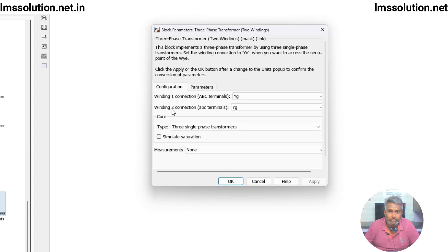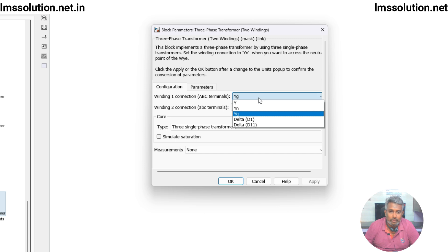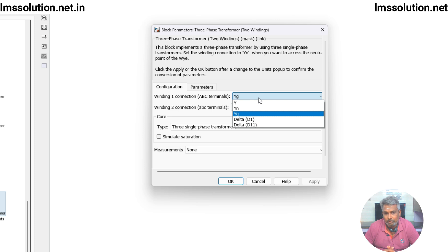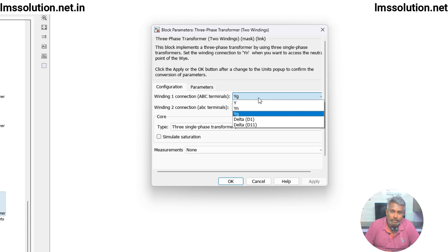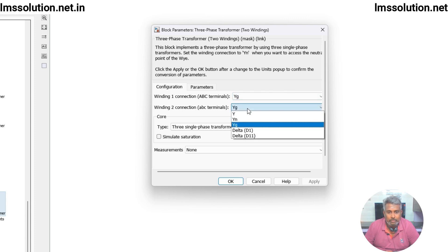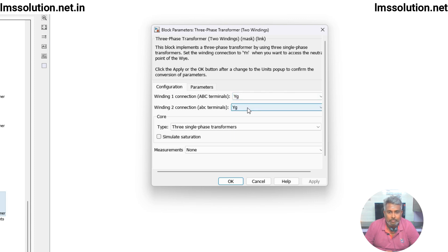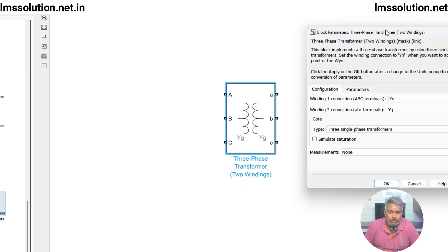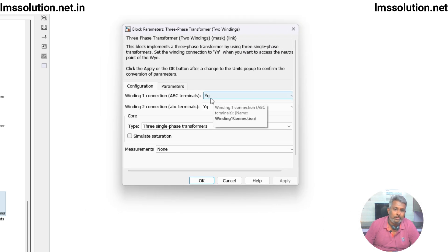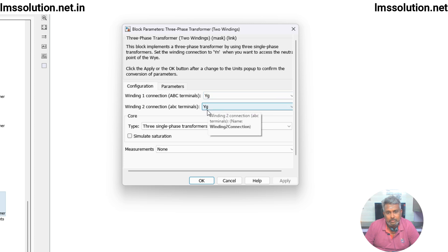In winding one you can fix any configuration: star, star with neutral, star with ground, or delta. For delta there are two configurations — D1 and D11. You can configure any type of network, whether delta or star. Here I am going to configure star-ground to star-ground.